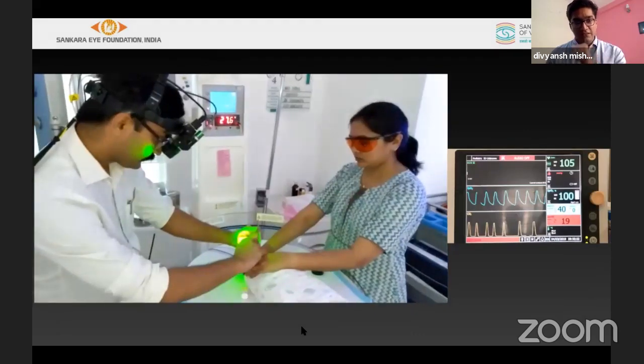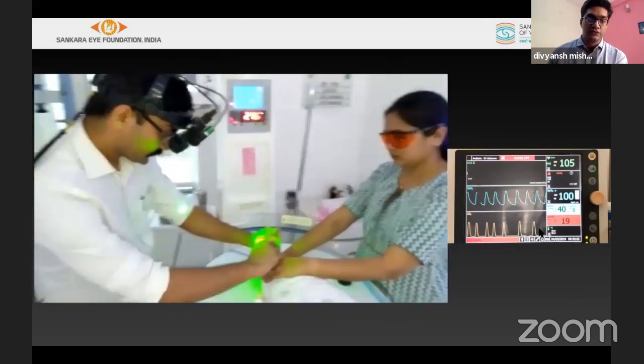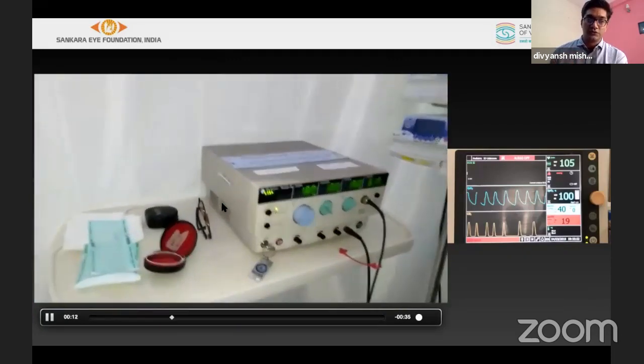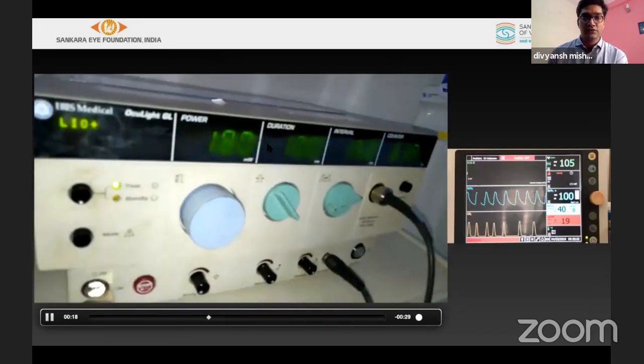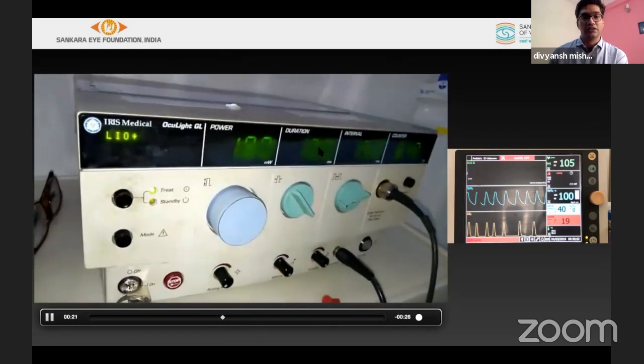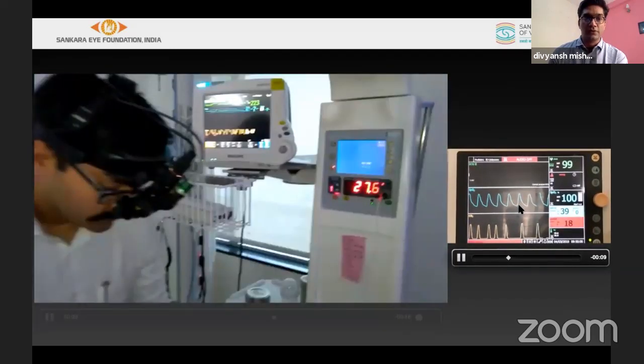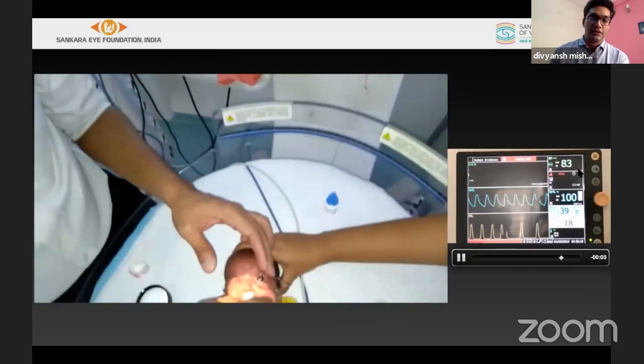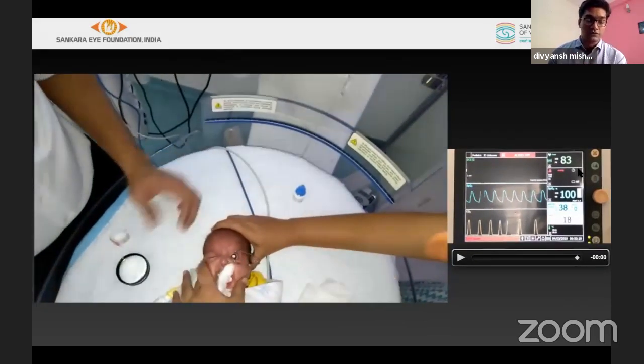When performing laser, dilatation must be done and the child must be comfortable and wrapped. Start with minimal power, probably at 175mW, and increase gradually if the burn response is inadequate. Duration can be set from 100 to 200ms and increased to 300ms. It is important to monitor the child's vitals in between, as apneic spells or bradycardia may occur. At that point, remove the speculum and stimulate the child. In rare cases, resuscitation may be needed.